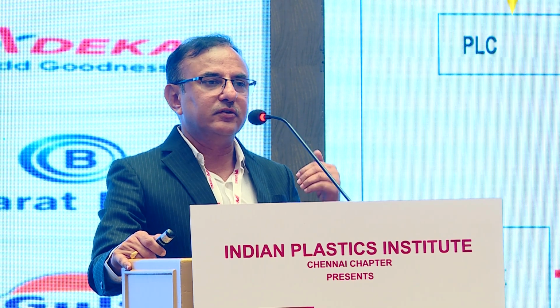So an internal gear pump, when it is driven by a servo motor and a KEB servo drive, gives you excellent energy saving, fast dynamic response and accurate flow and pressure control. So what is the benefit of this? The article manufactured in the machine will have very good quality, lower rejections, and production will also increase. Besides, unlike an induction motor, which draws 30% no load current, the servo motor will draw just 1 ampere under the no load condition, and you will be able to accelerate the servo pump with the servo motor and drive very fast, very quickly, without any wastage of energy.